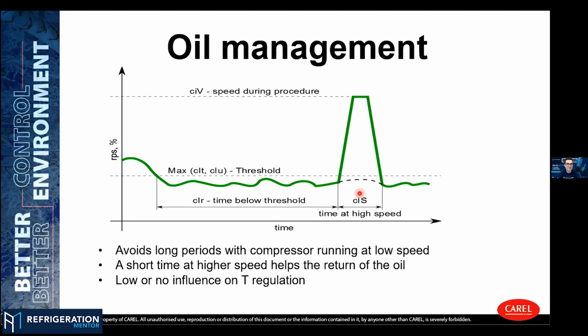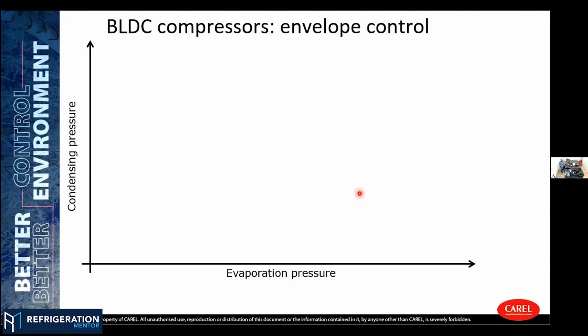Yeah, right. Most of the controllers now show on the main screen the speed of the compressor, the opening of the valve, and also the status. We will see on the inverter side, on the envelope side, zones like zone 1, zone 2, and it will say oil recovery zone, so we are recovering oil to the compressor. Talking about the famous envelope control, I'll try to draw some images and show you what it is.